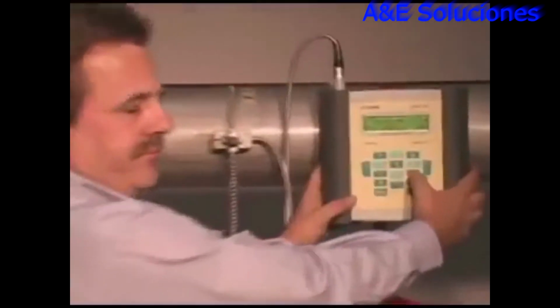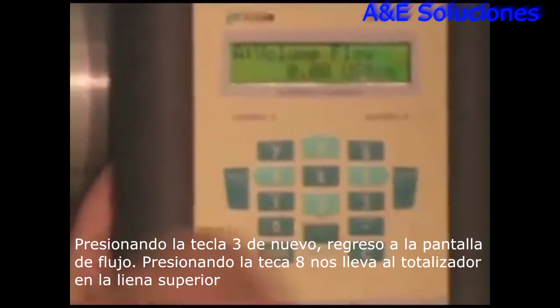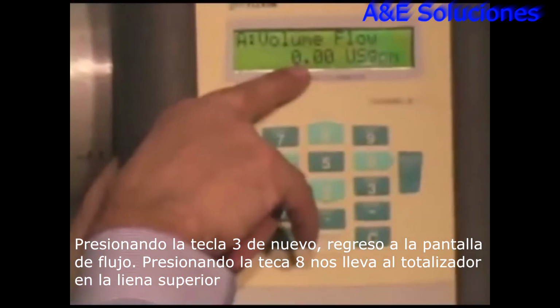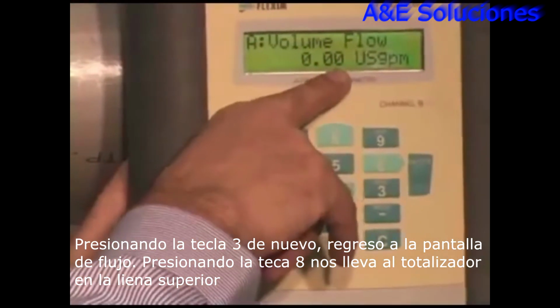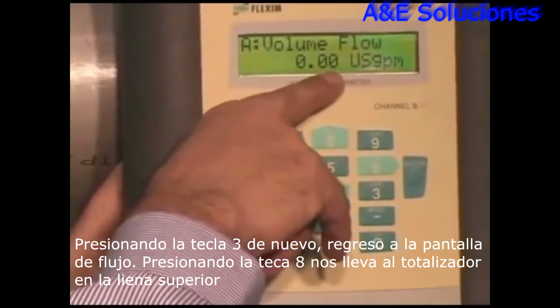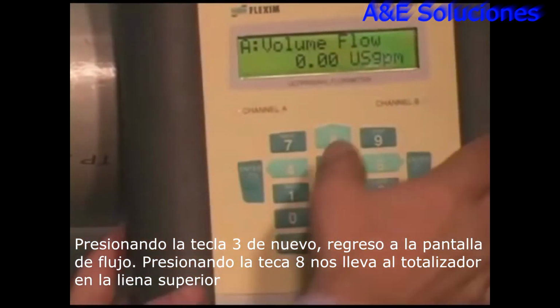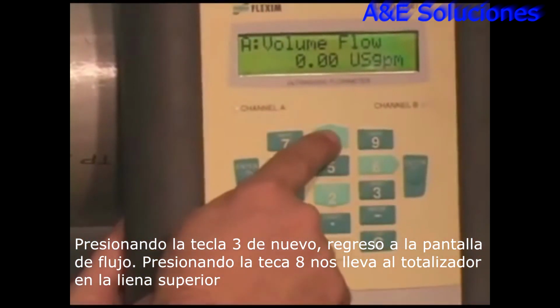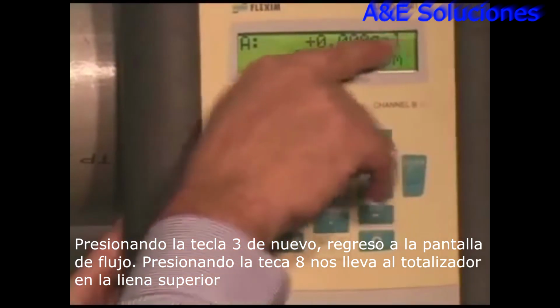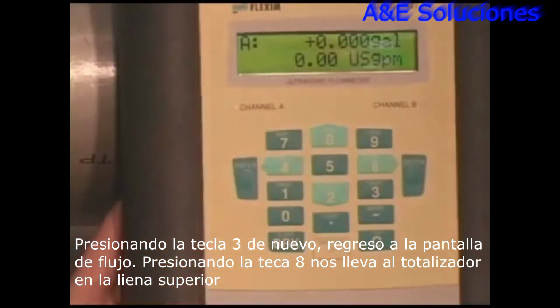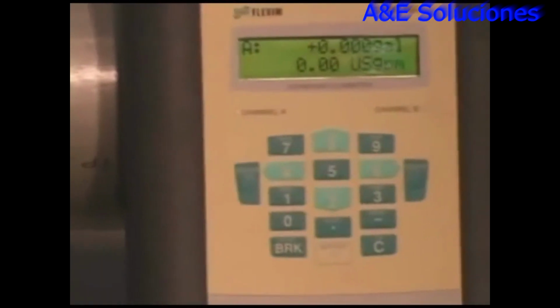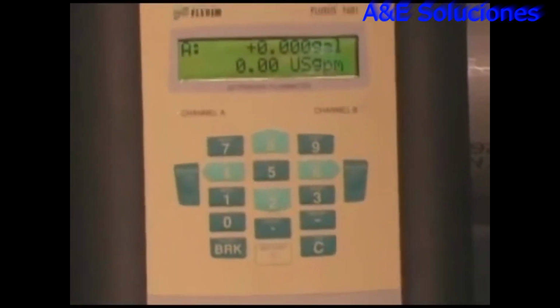Okay, so if I hit the 3 key again, I get back to the flow screen. So it just toggled that bottom line. It went from gallons per minute to flow velocity to sound speed. Okay, now here, this button here, the 8 key, is Q on. That's our total. So if I press that, it turns on the totalizer on the top line. So now we're going to turn on the flow a little bit here for you. We'll show you that the meter actually measures flow.